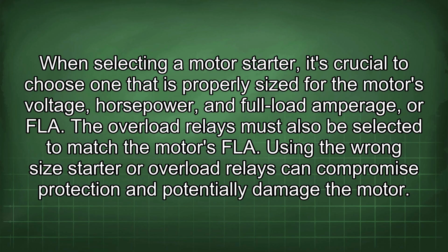When selecting a motor starter, it's crucial to choose one that is properly sized for the motor's voltage, horsepower, and full load amperage, or FLA. The overload relays must also be selected to match the motor's FLA. Using the wrong size starter or overload relays can compromise protection and potentially damage the motor.